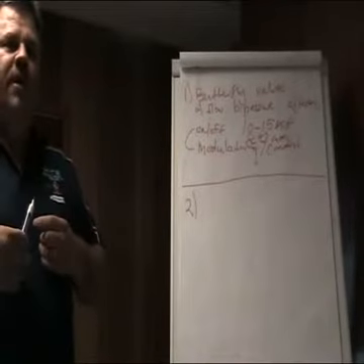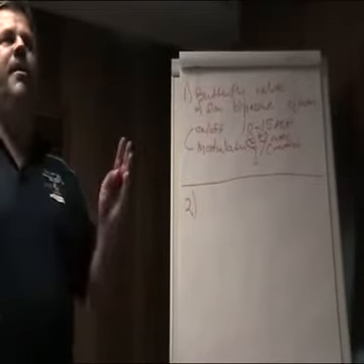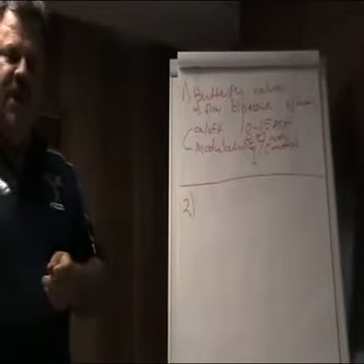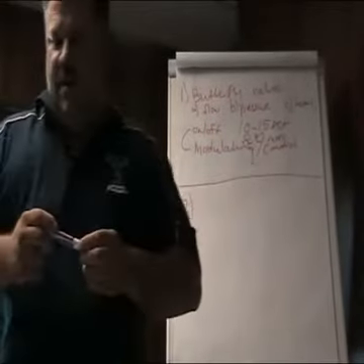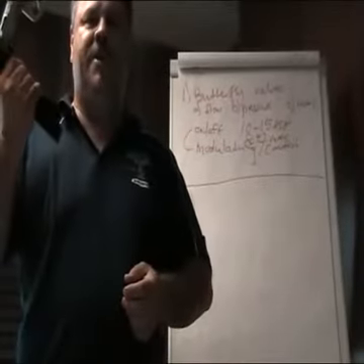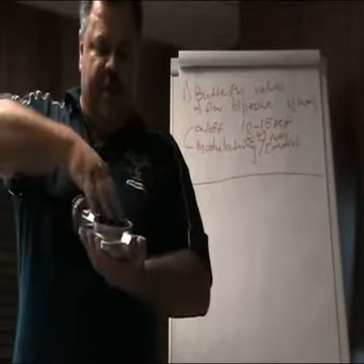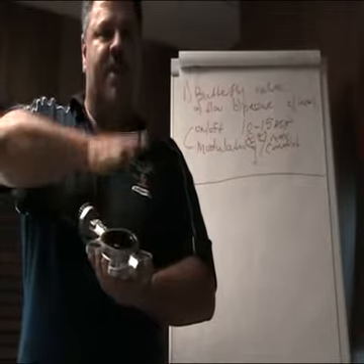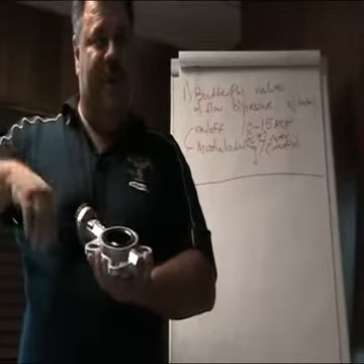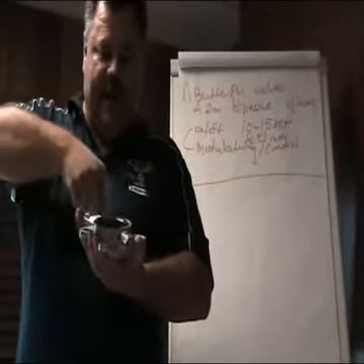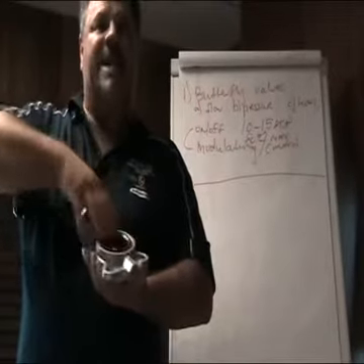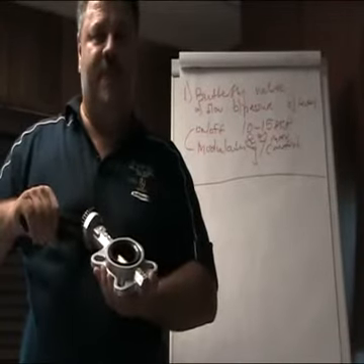What's the difference between the low pressure and high pressure side? Okay, the pressure, yeah. But I mean in the construction of the valve. Not so much the pressure, it's differential pressure. Differential pressure, big issue. Because if you've got a big differential pressure across, this thing is going to go, the liners. The difference between a soft rubber lined low pressure butterfly and a high pressure disc valve is the fact that you don't have a liner like this. Everything is metal.